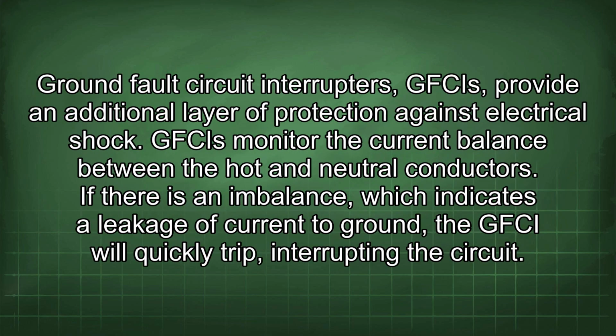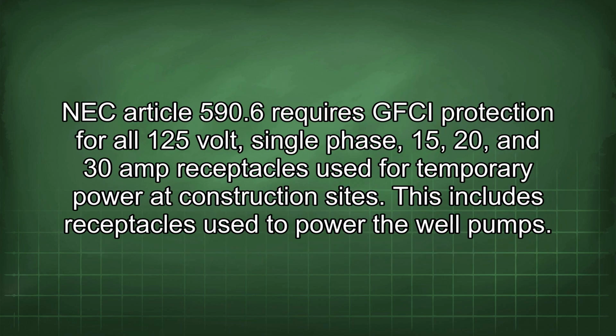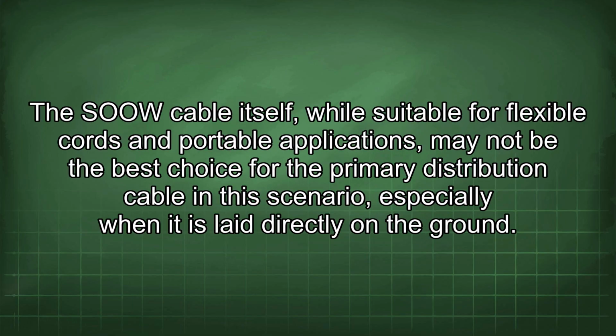Ground fault circuit interrupters, GFCIs, provide an additional layer of protection against electrical shock. GFCIs monitor the current balance between the hot and neutral conductors. If there is an imbalance, which indicates a leakage of current to ground, the GFCI will quickly trip, interrupting the circuit. NEC Article 590.6 requires GFCI protection for all 125-volt, single-phase, 15, 20, and 30-amp receptacles used for temporary power at construction sites. This includes receptacles used to power the well pumps. The SOOW cable itself, while suitable for flexible cords and portable applications, may not be the best choice for the primary distribution cable in this scenario, especially when it is laid directly on the ground.